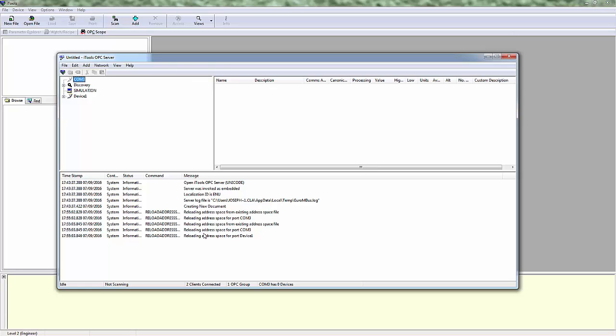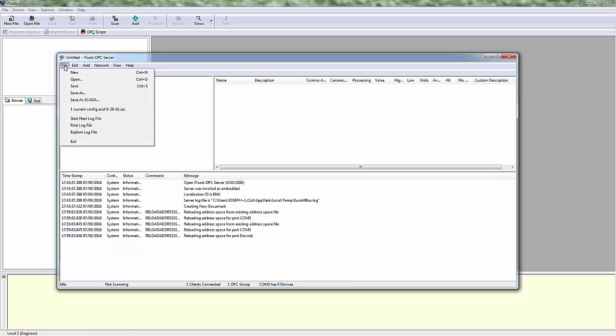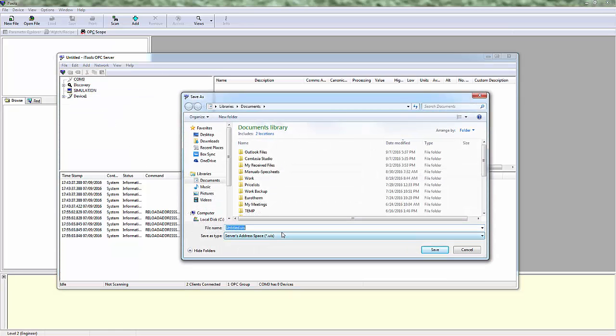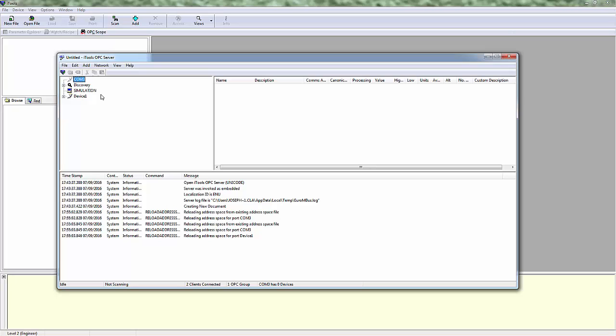If you use the OPC Server to set it up, my suggestion is to go to File and Save As, then label the configuration. The reason is that when you add a device to OPC, you need to make sure iTools is looking at that particular configuration. You can also set it to use this configuration every time. That way you can have different OPC Server configurations depending on the application. One important thing: when you're done, don't hit the X to close. Go to View, Hide Server. If you do exit out, it will pause for five to seven seconds, give a warning, and if you close, you'll have to restart iTools — it's just more trouble than it's worth.